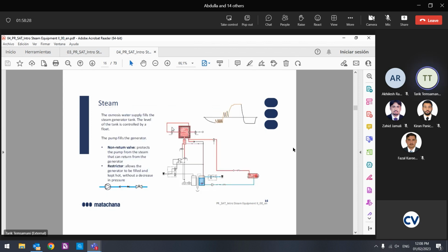Both have to work together actually. So this one is open, we are filling that, and this one is open, we are filling that. So it should go on and off. When this is on, this should be off. But what can happen here? I will ask you, and I will answer you. What can happen here? I am getting steam from that to the chamber, and in the chamber I am making water, cold water. So to get steam, maybe I don't have enough production of steam to fill. Yes, a drop in pressure can happen.